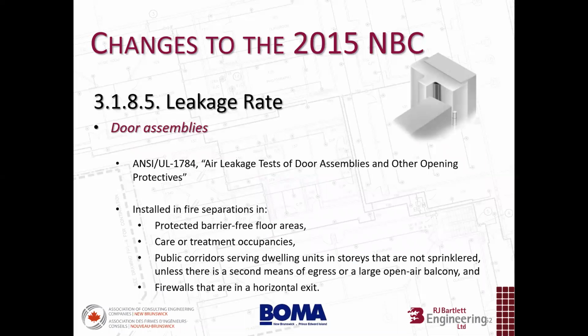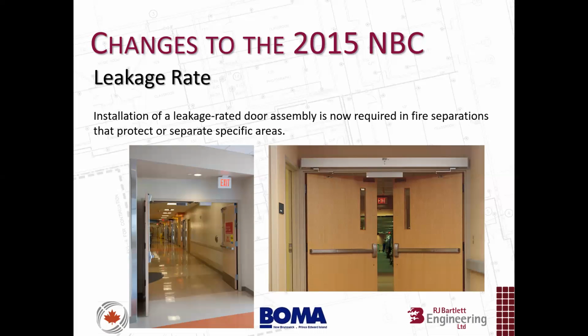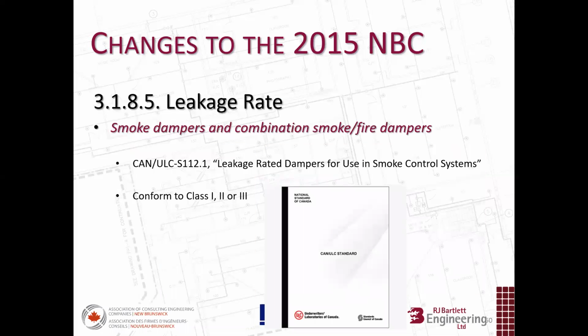Hi, Steve. Hi. Mind if we go? I do have a question here about the fire dampers. Okay. Great. The question is, if fire dampers are waived for commercial kitchen exhaust, does that mean that when a commercial kitchen exhaust duct penetrates a required fire resistance rating, that no additional protection is required? Yeah, that's a good question.